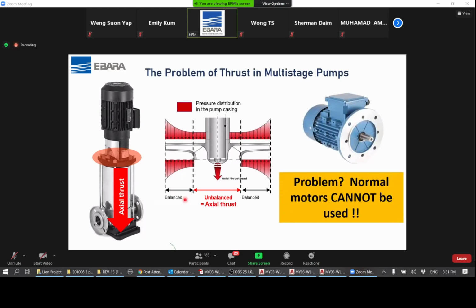Now, the problem is that this thrust has to be taken up somewhere, and the only way is either through the foundation of the pump, but because of the force, the motors will have to absorb some of this thrust. That is why a very important fact is that for a multi-stage pump, normal motors cannot be used. When I say normal motors, it means the standard motors that you buy from the supplier. You will need a motor that has a special thrust bearing, and this means more cost.